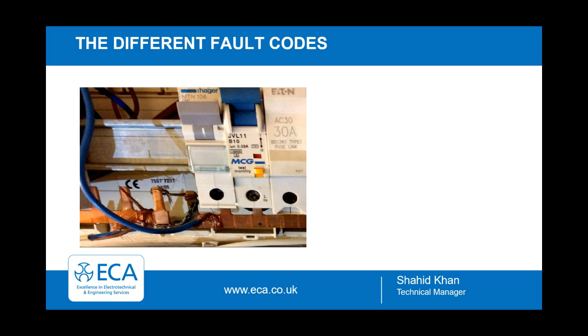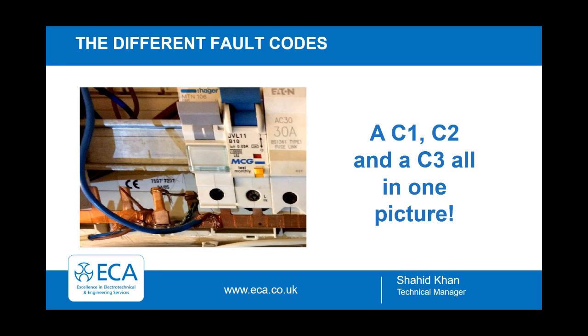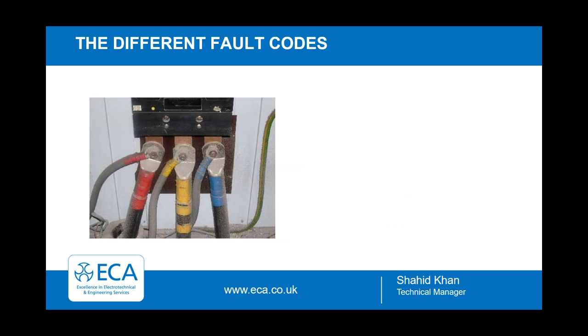What about this picture? There's quite a lot wrong with this one, isn't there? I was going to say, where do you start? Mixed breakers, and conductors wrapped around bus bars. It looks like there's a neutral as well that's wrapped around the bus bars. It looks blue to me. So wrong cables. So a raft, you could potentially pick up a C1, C2 and a C3 all in one picture there. Somebody's just put too many to mention. I think he's hit that one. I'd agree with that.